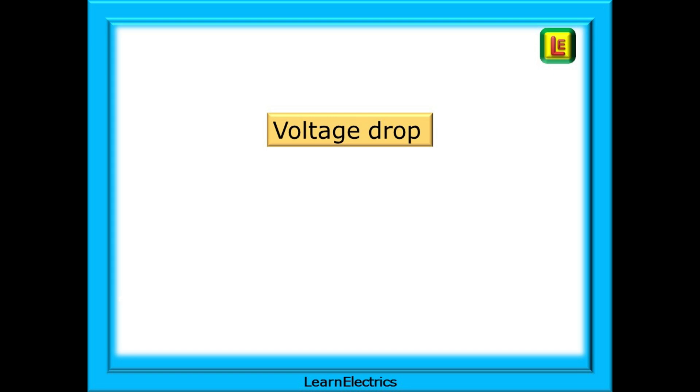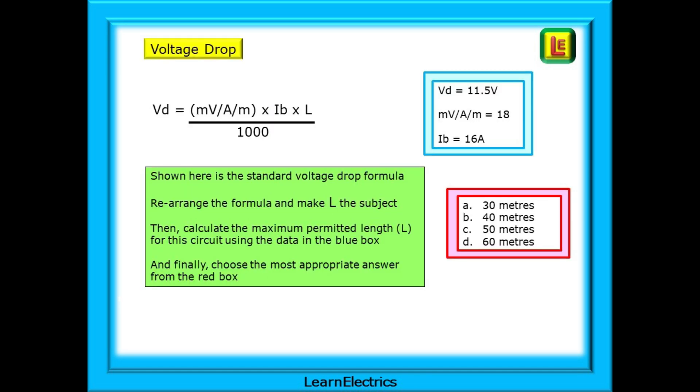And lastly, for these essential formulas, we can take a look at voltage drop in standard copper cables. Shown here is the standard voltage drop formula. You are required to rearrange the formula and make L the subject. Then, calculate the maximum permitted length L for this circuit using the data in the blue box. And finally, choose the most appropriate answer from the red box. Pause the video while you work through the task. Answers on the next slide.